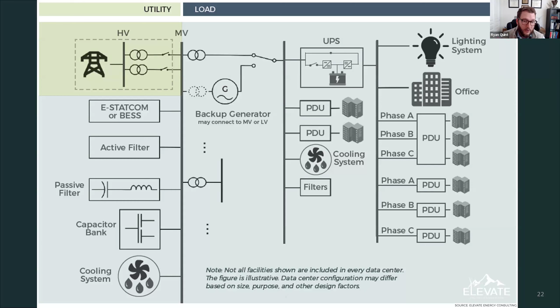There's not a lot of data out there to tell us what the load composition of a data center looks like. This is some information pulled from the Western Interconnection load model tool, which is publicly available, and I think they got pretty close. They had done analysis and said over the course of a day, a typical data center is mostly power electronic load, 80+%. They've got some motor load, although most of that is used for cooling, and most of that is now power electronic connected through variable frequency drives. So the power electronic load may be even higher. But now the performance of these power electronic components is quite different, and we have to start thinking about that.